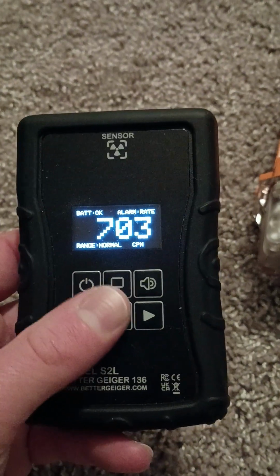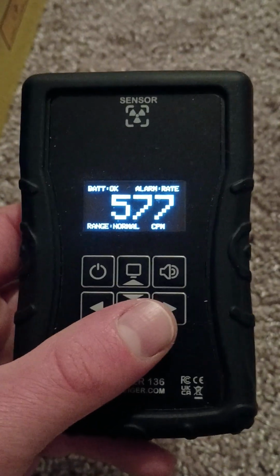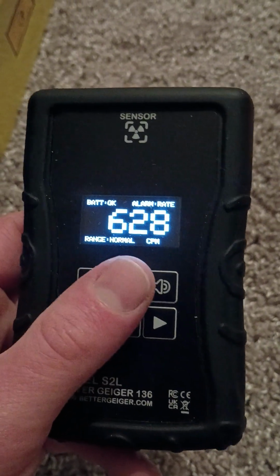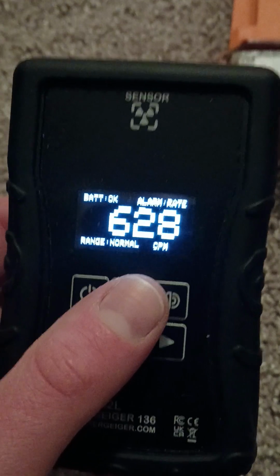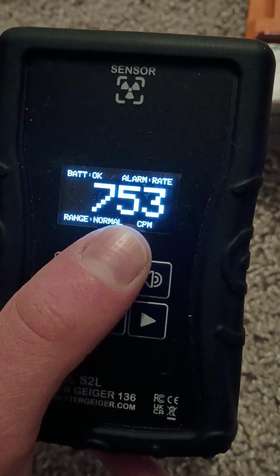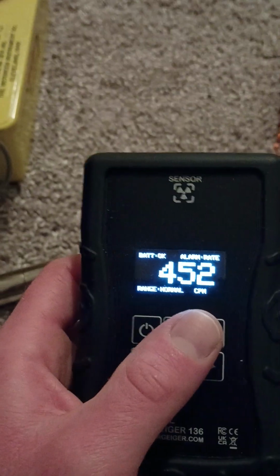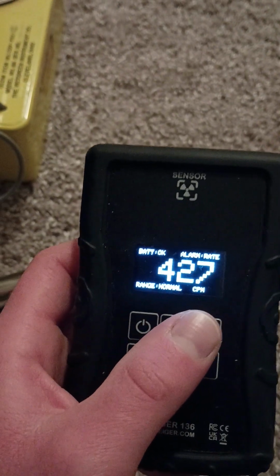All right, let's try this one that I just got in. This is a Better Geiger S2L. It's one feature up from their standard S2 model. It has a larger scintillation crystal than the standard model, and in fact has a larger scintillation crystal than this one, the Radiacode 102. So the background count is going to be significantly higher. Now, background where I am tends to be about 300 to 800 at the very most. And again, just going to put this right here.